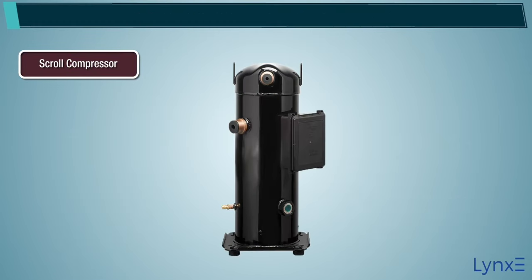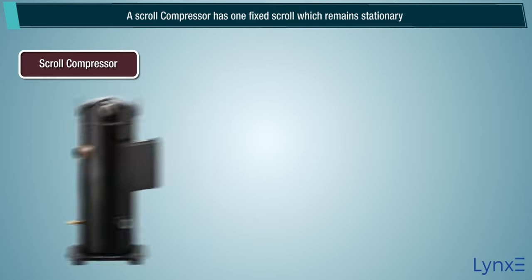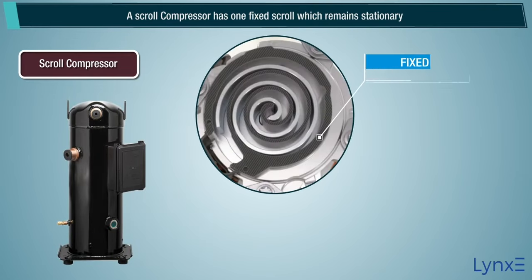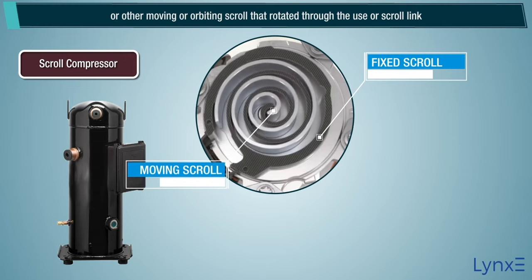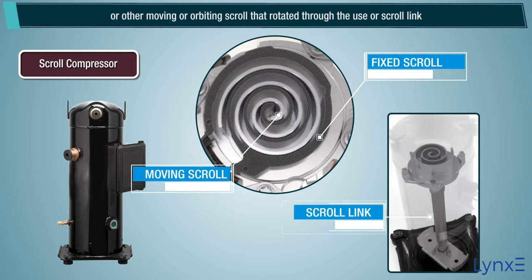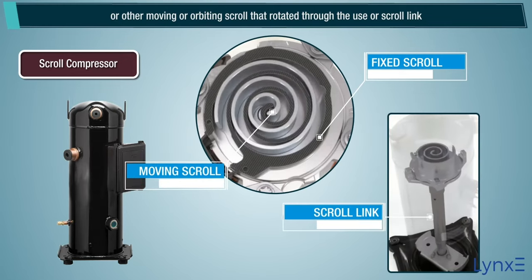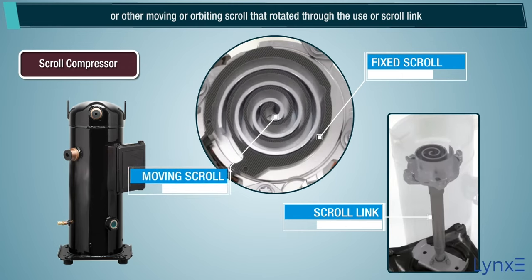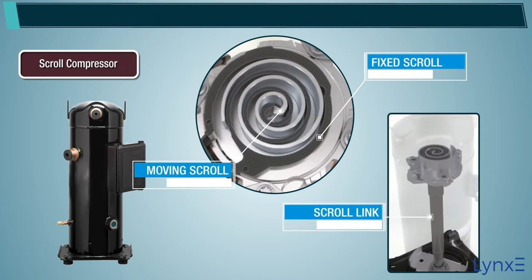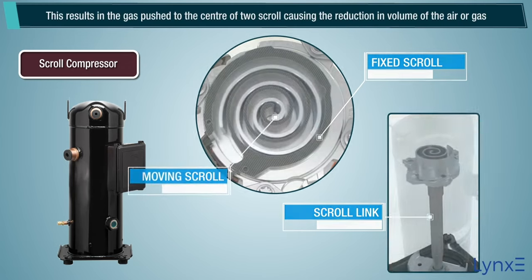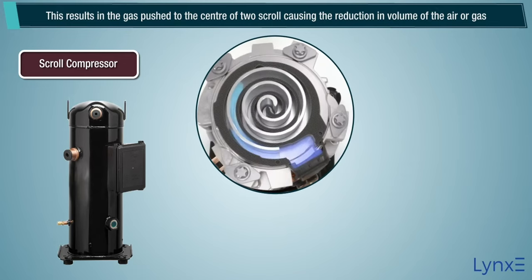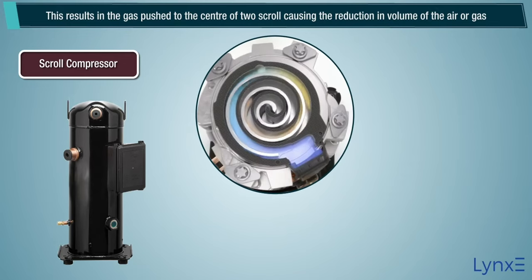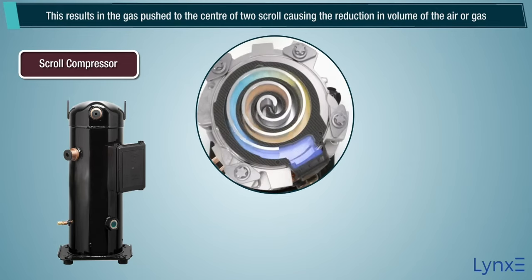A scroll compressor has one fixed scroll which remains stationary and another moving or orbiting scroll that rotates through the use of a scroll link. This results in the gas being pushed to the center of the two scrolls, causing a reduction in the volume of the air or gas.